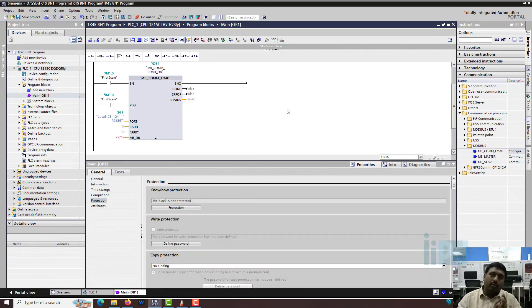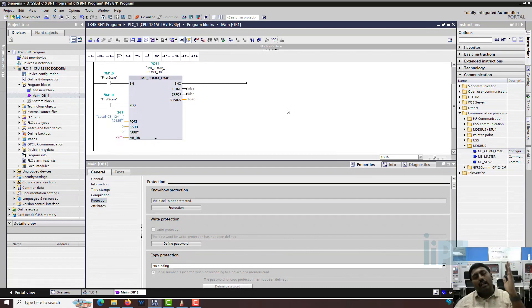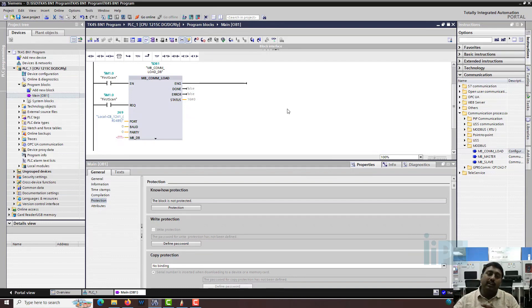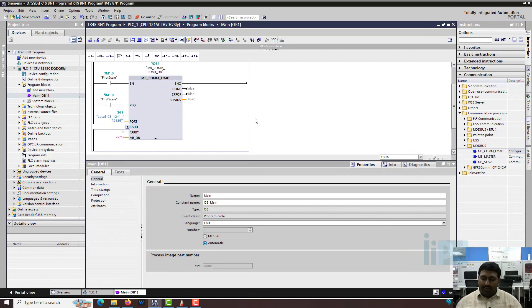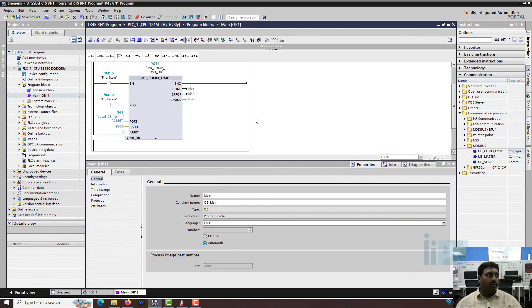If you have two Modbus modules - one in the CPU as a communication board and one in a left-hand extension module - you will have two options: 269 and perhaps 270. The hardware identifier number changes as you add devices. Next, enter the baud rate: we will use 9600. The parity will be zero - zero means no parity, one means odd parity, two means even parity. We are going to use zero parity.